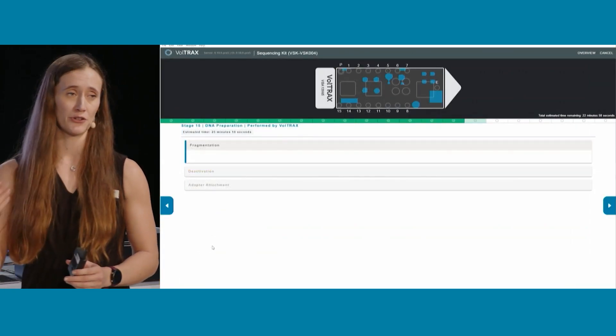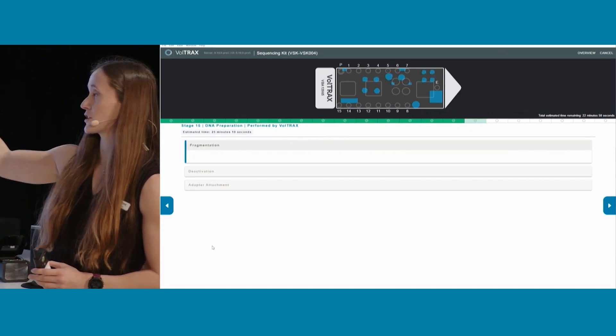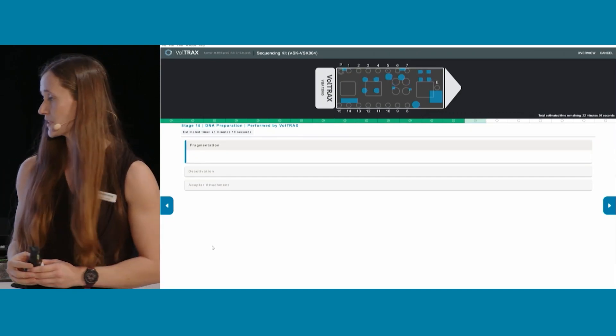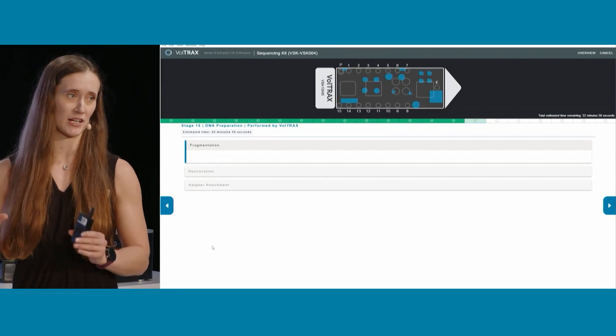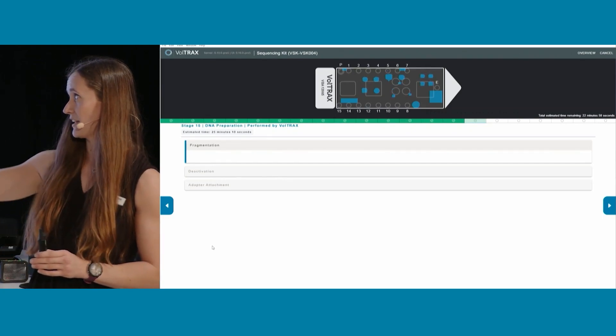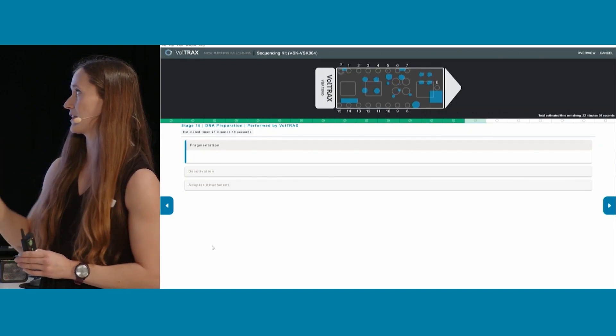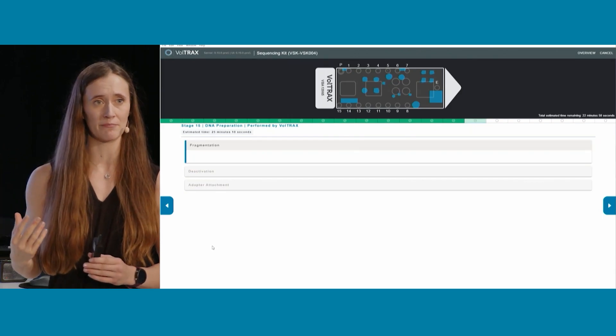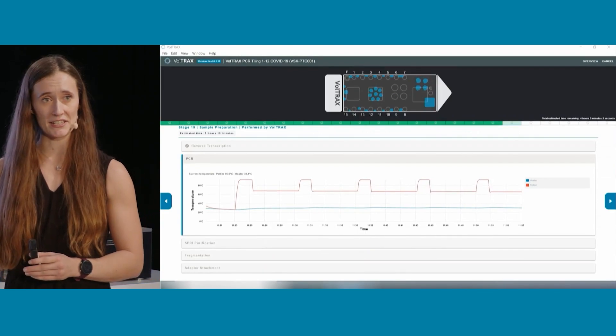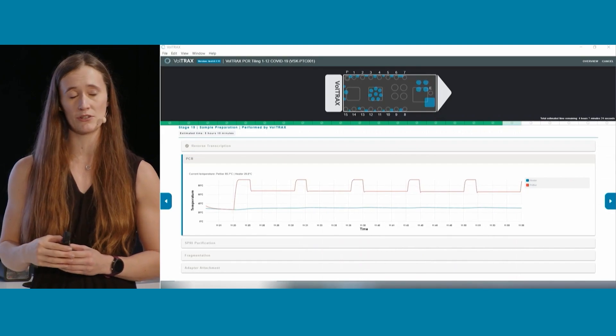When you click continue and have loaded all your reagents, it comes to a screen with a visual representation of what's happening on the cartridge — showing you what all the liquid is doing, where it's going, and what's being dispensed. It tells you what step you're on, and gives you an estimated time remaining for the protocol.